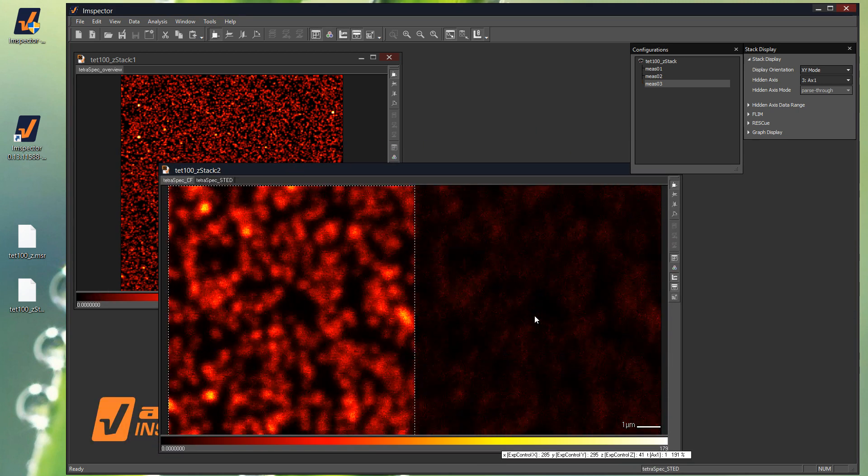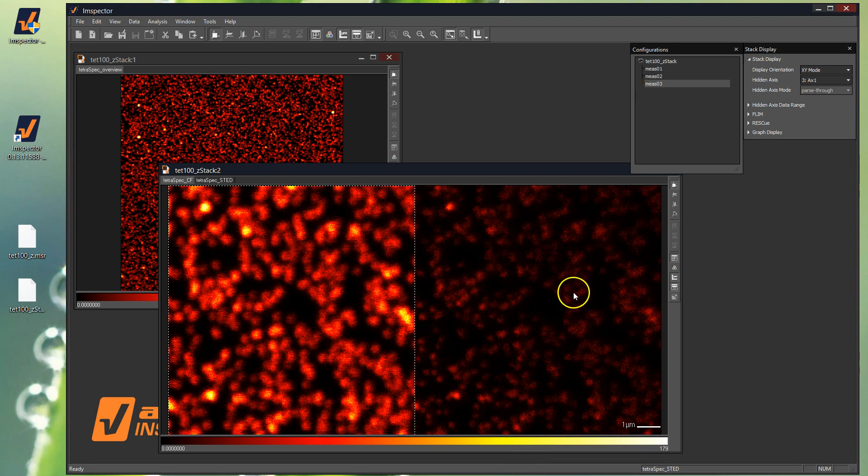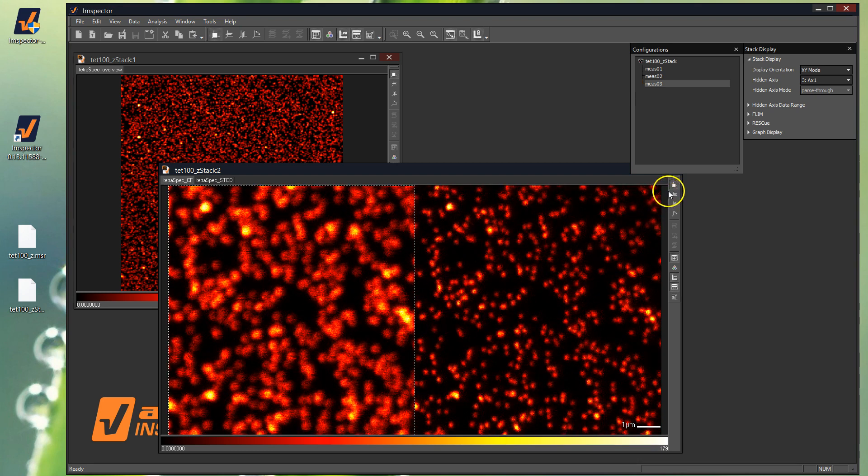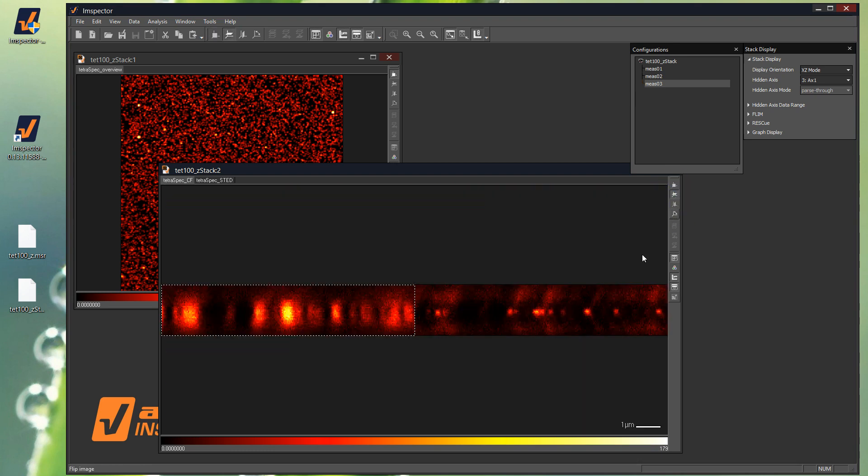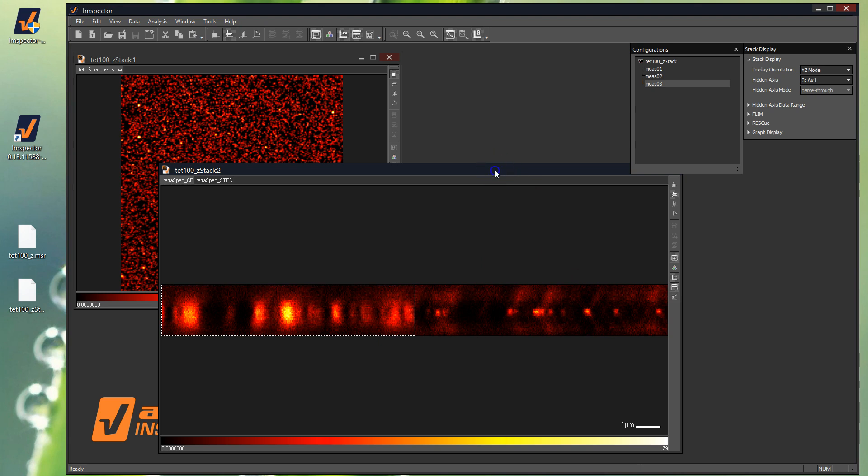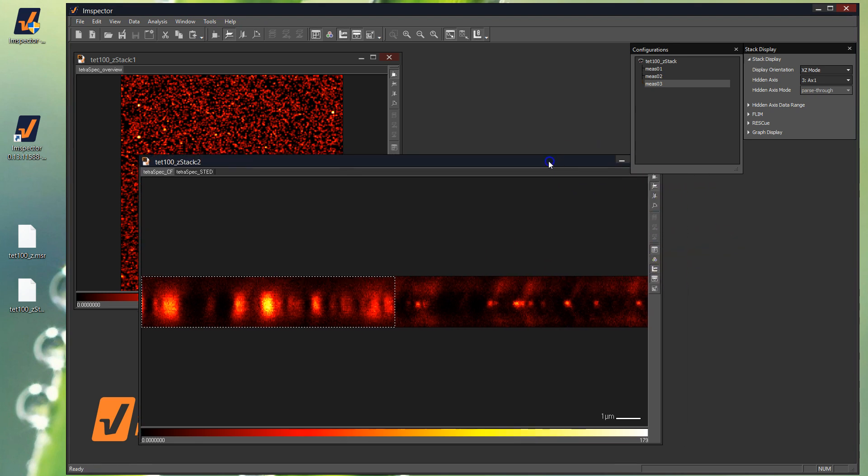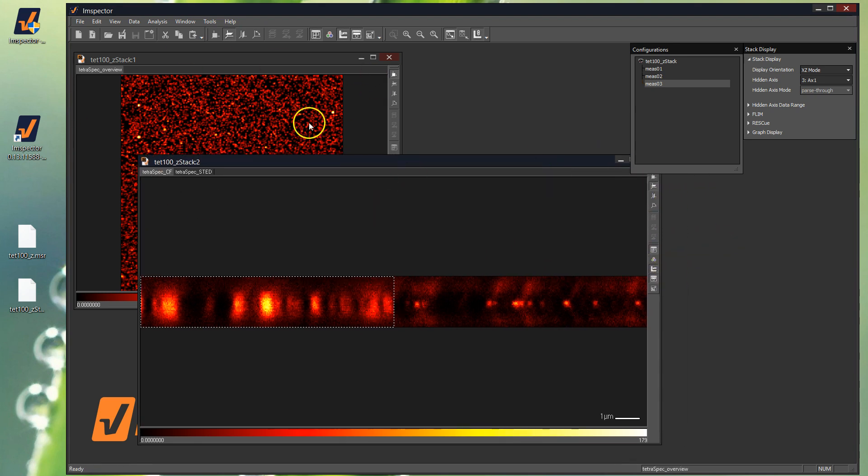It will show you the STED and the confocal data here. There's no Z, so I used the mouse wheel to go through. There are buttons down here, down the side for looking at different views, the side profile. These were from playing around with scopes. These aren't perfectly aligned, but you can definitely see the STED improvement. The point spread function wasn't great, so we had some tweaking to do, but this was just during that process.